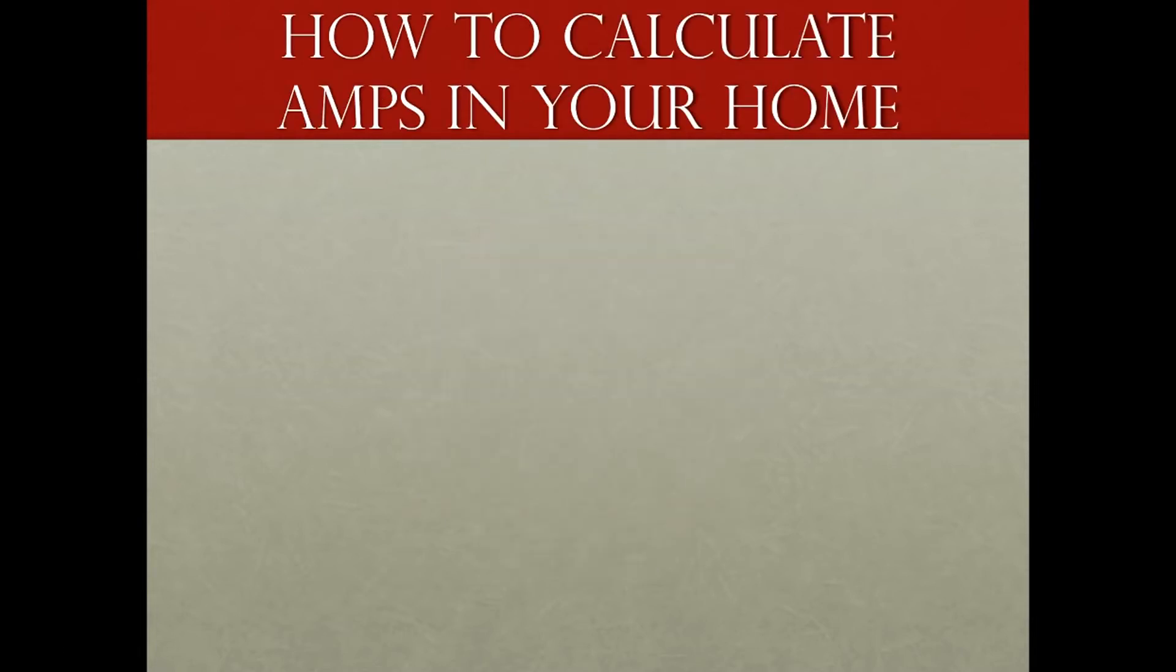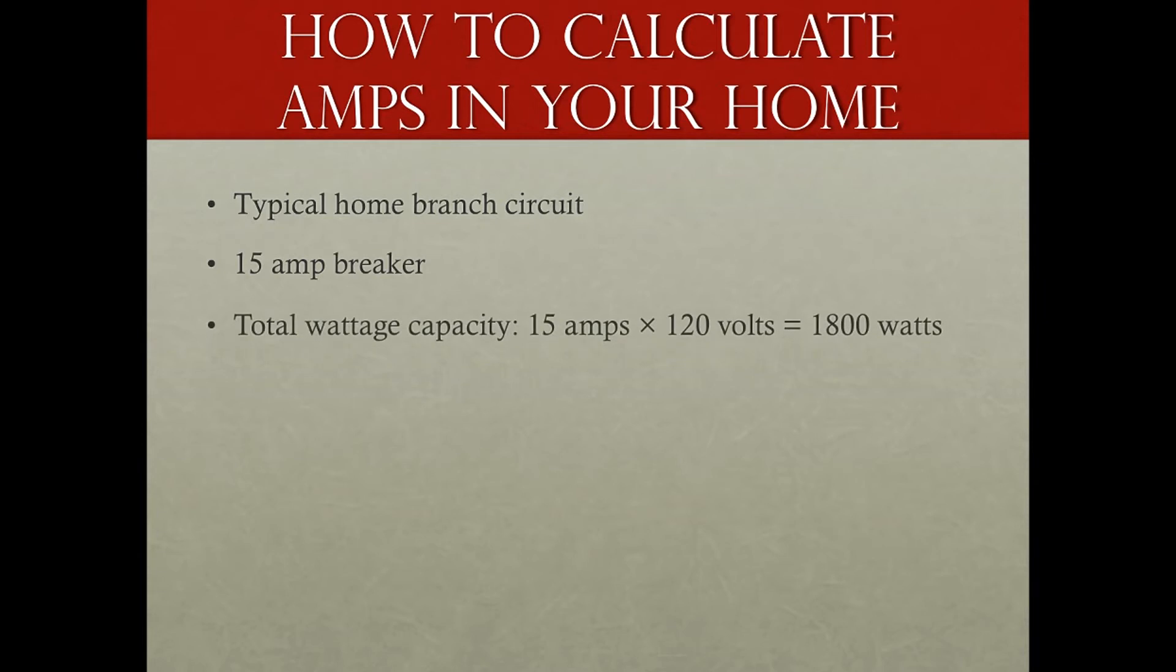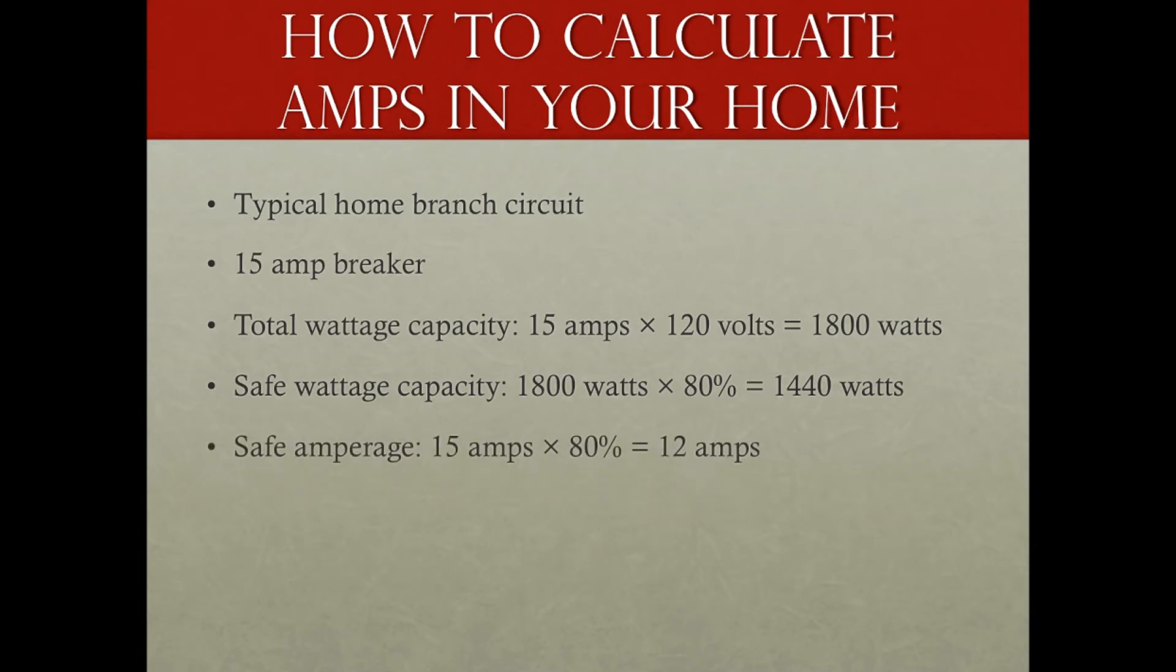So let's take something we haven't gotten into the circuits yet. Let's take something we can all wrap our head around, that is amps in our home. So if we want to take a typical home branch circuit, say we had one like a 15-amp breaker, and you could use that on something like lighting. Typically they use like 20 amps on receptacles. But this is just an example. So we'll take a total wattage capacity is 15 amps times 120 volts equals 1,800 watts. Now there's always a safety or a fudge factor that you want to calculate in there. So we take the safety wattage capacity is 1,800 watts, and we always multiply that by 80%. It gives us 1,440 watts. And our safe amperage would be 15 amps times the same factor, 80% gives us 12 amps.